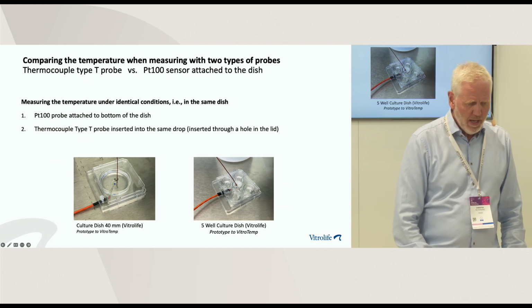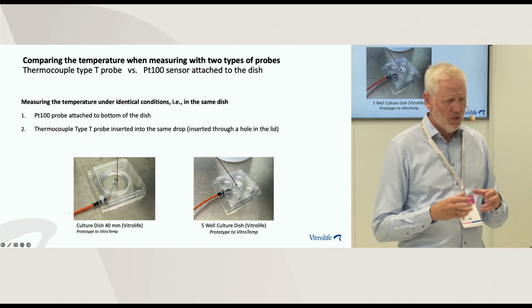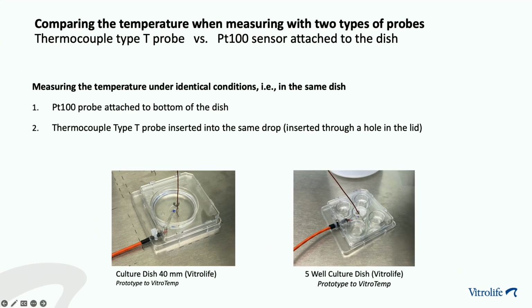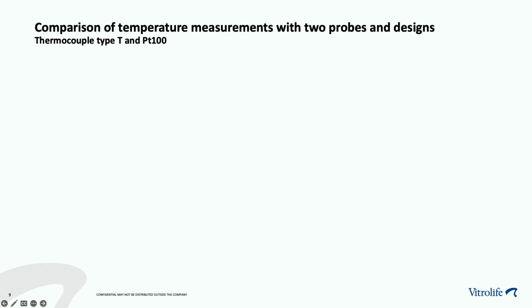So we have compared the temperature by using these two probes just to see what differences we see. We have taken Vitrolife's 40 mm dish and Vitrolife square dish, and we have built a thermocouple in. We have a thermocouple type T that we placed in a droplet, and we also have attached a PT100. This is a prototype of the VitroTemp, so it's the same principle. And now we can measure the temperature and see what the two probes give in results. And this is what we found.